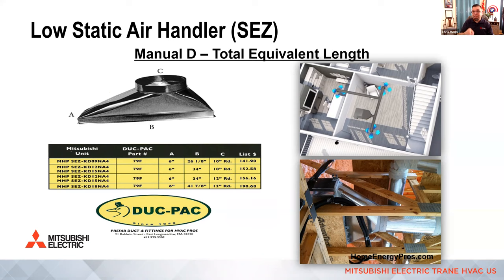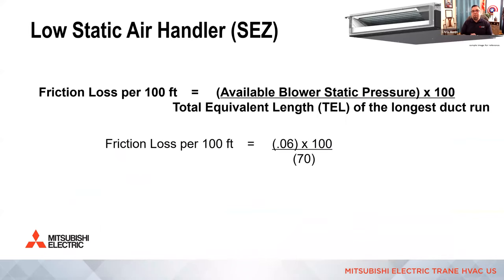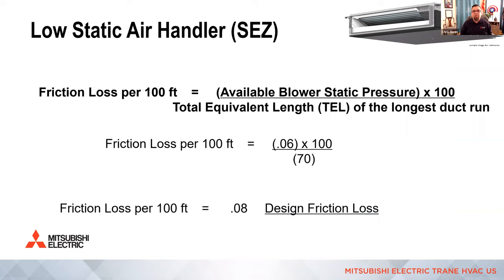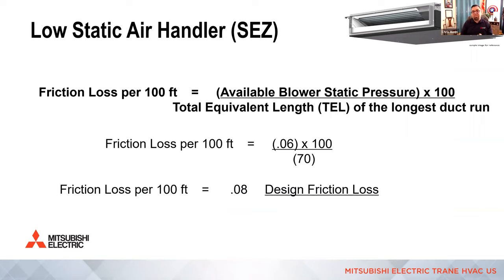We're going to get to that particular thing as an example as we go to the mid and high static, okay? All right. So the math on this particular low static air handler works out like this. Your friction loss per 100 feet, we just plug in these two numbers. If you remember, there's 0.06 available times the constant of 100 divided by 70 feet in that example. So you see it's very small amount of ductwork and equivalent length. And you'll notice the design friction loss works out to 0.08.